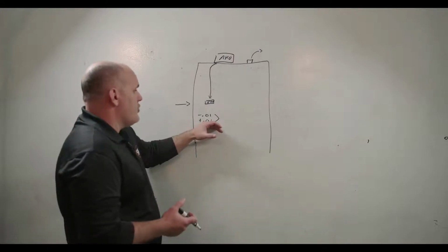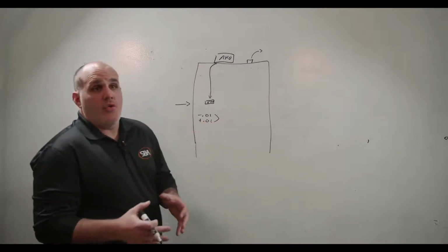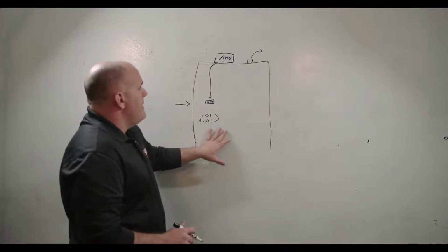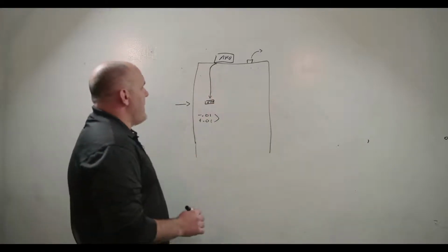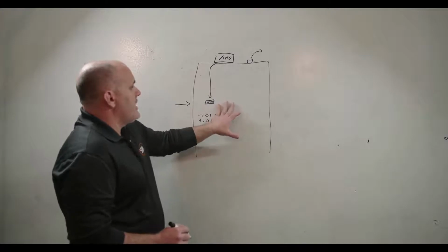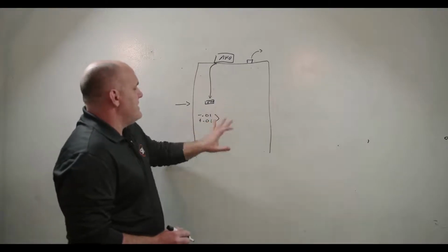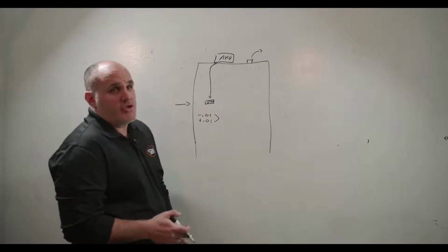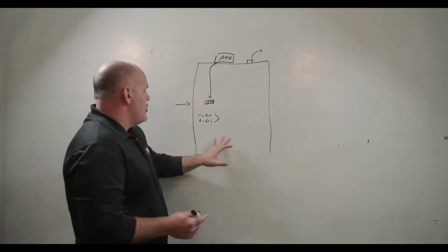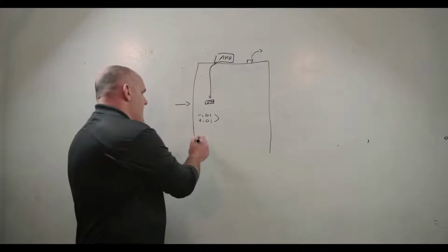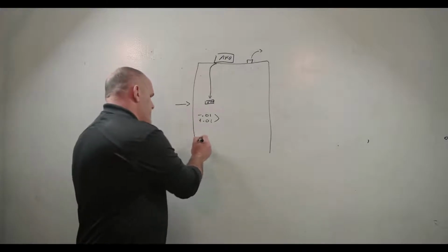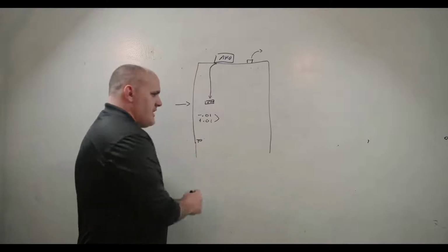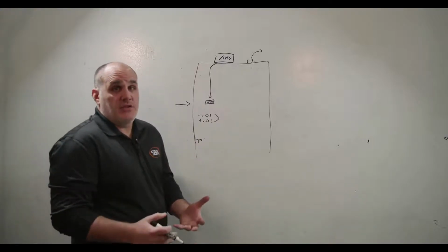So you're going to have a greater positive pressure in order to force that air out, to keep it from coming in. But if we blow this up, if we expand this and start to look at pressure control within the spaces, typically you're not going to experience pressure control within the spaces. Typically, you're going to make a selection of saying, hey, we're either going to put our building pressure sensor at the door, at the entry to the building, and in which case we're going to have to do signal filtering.